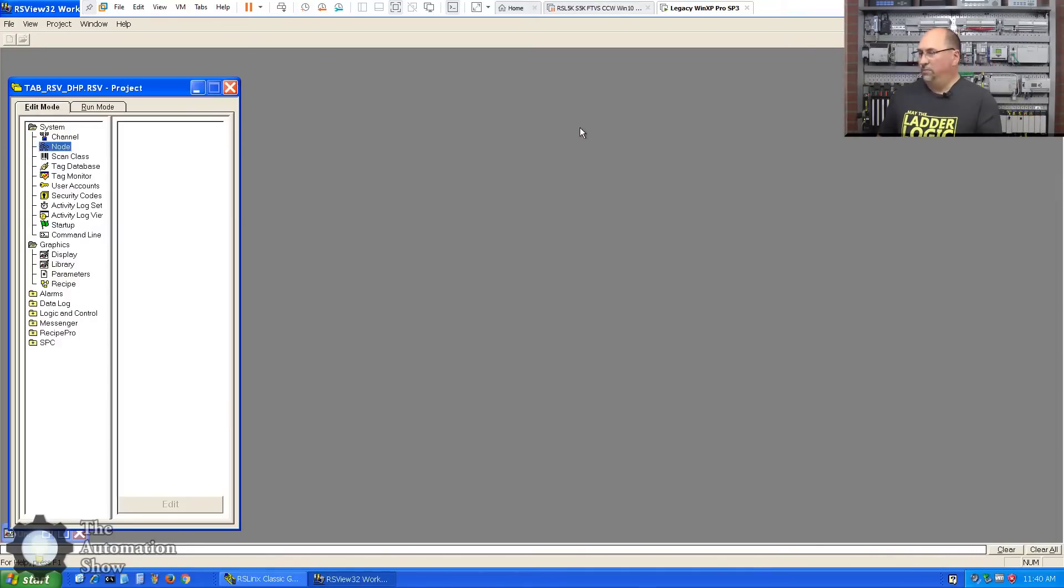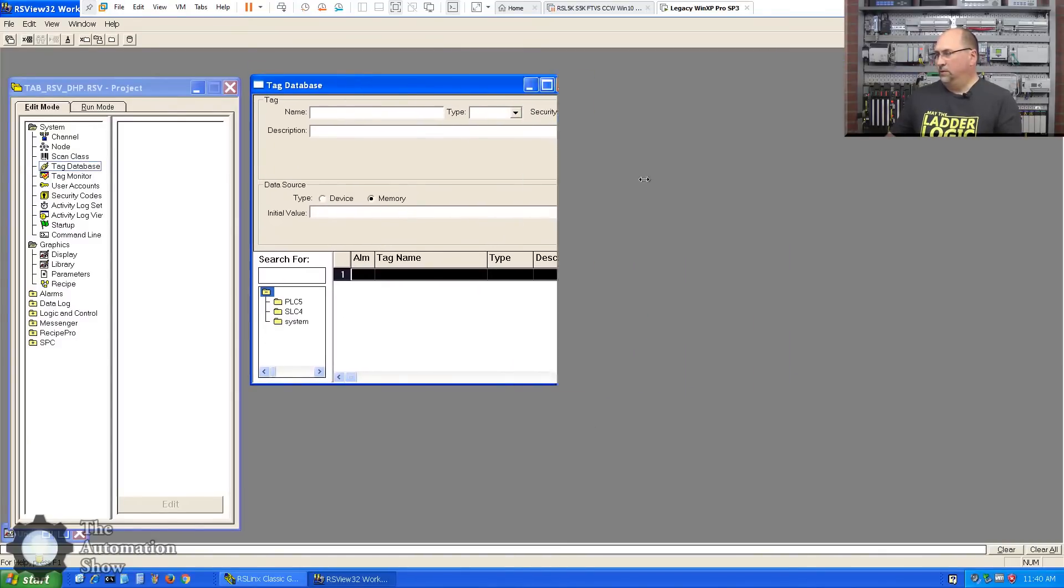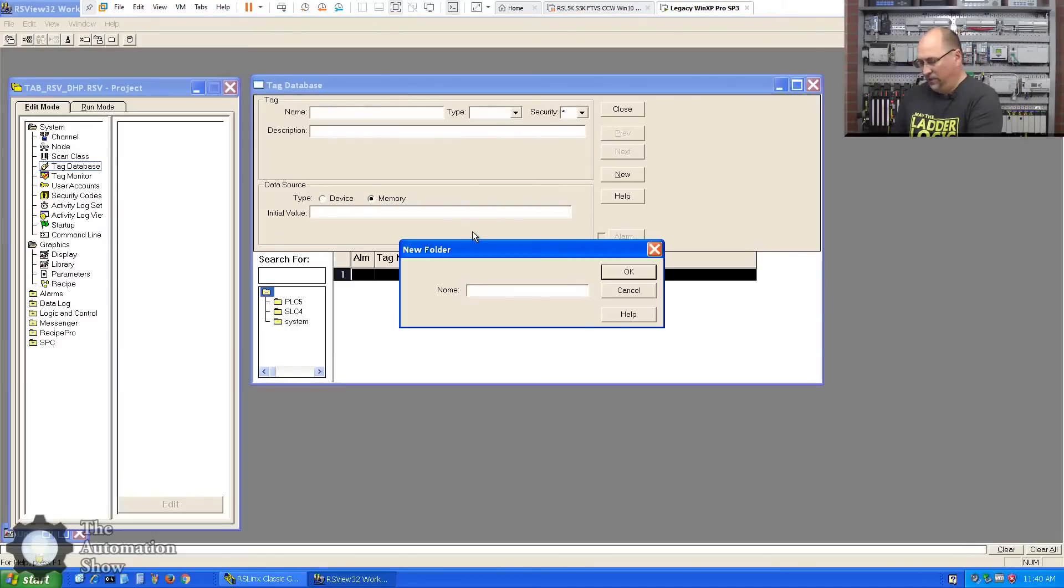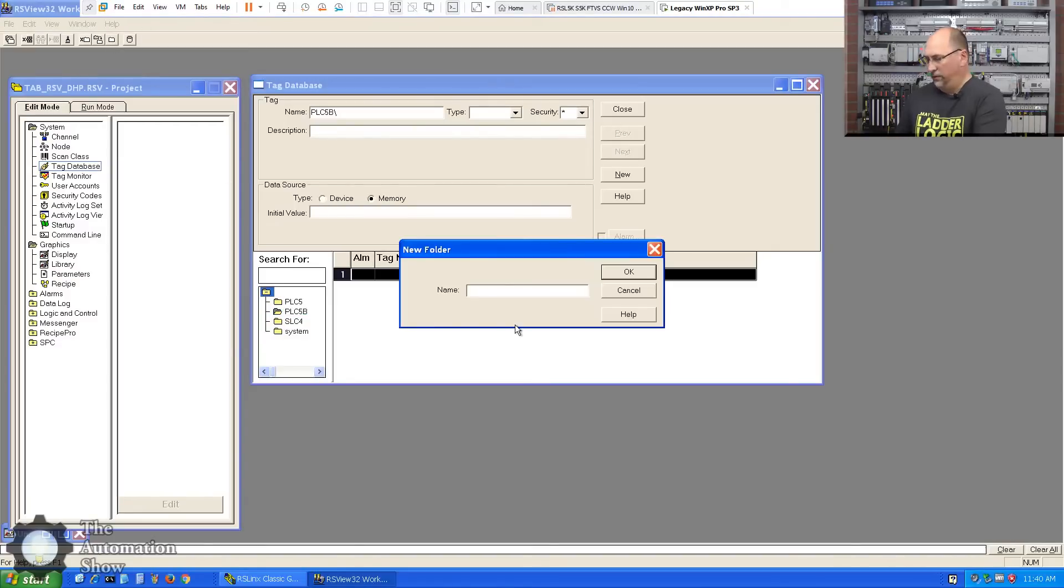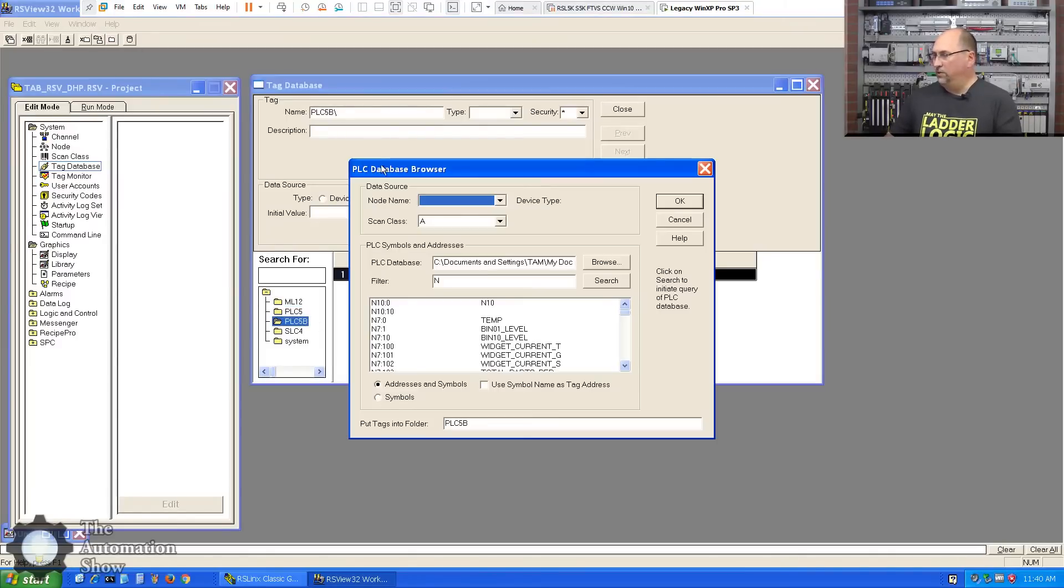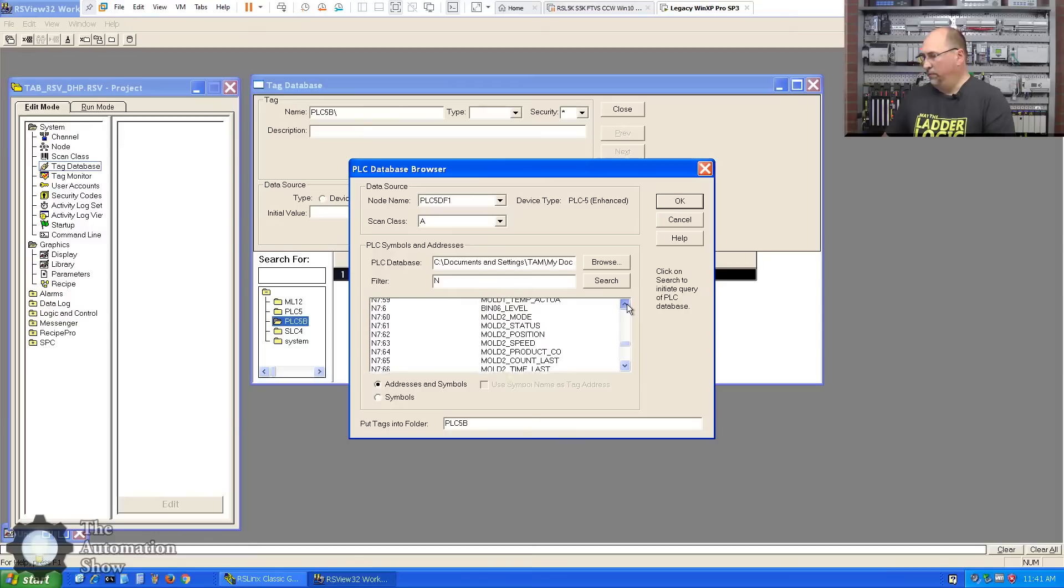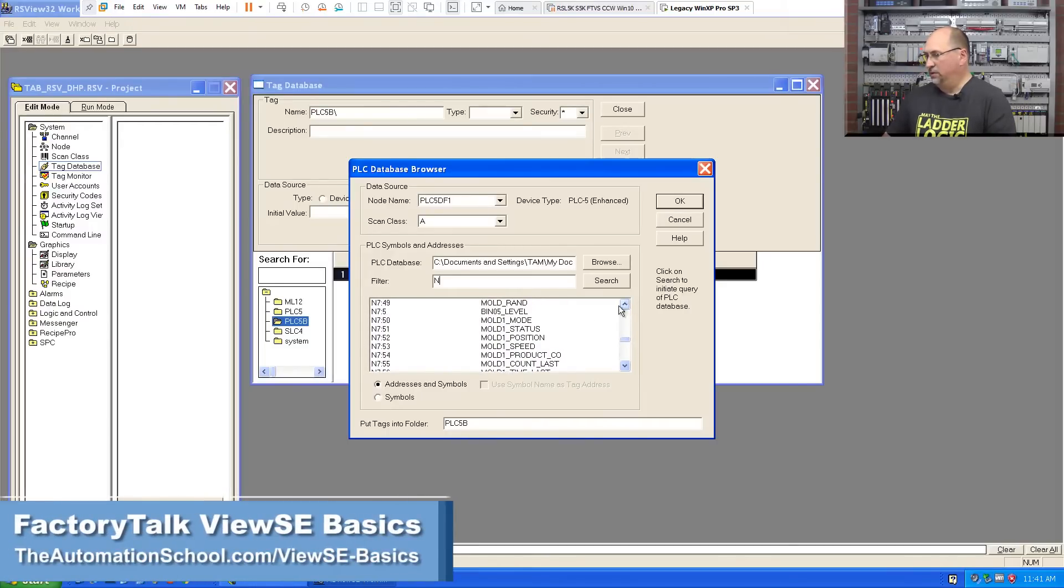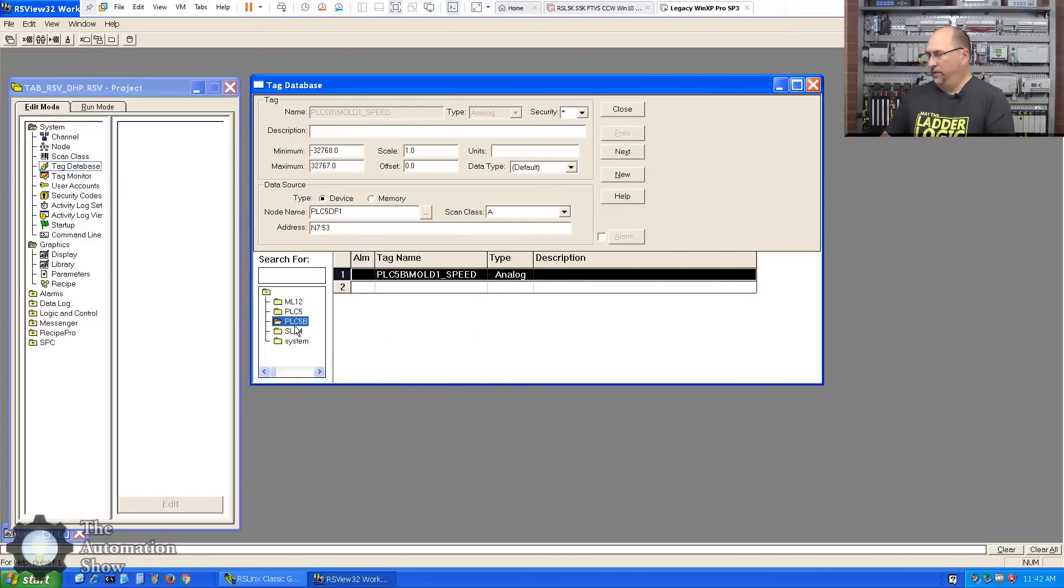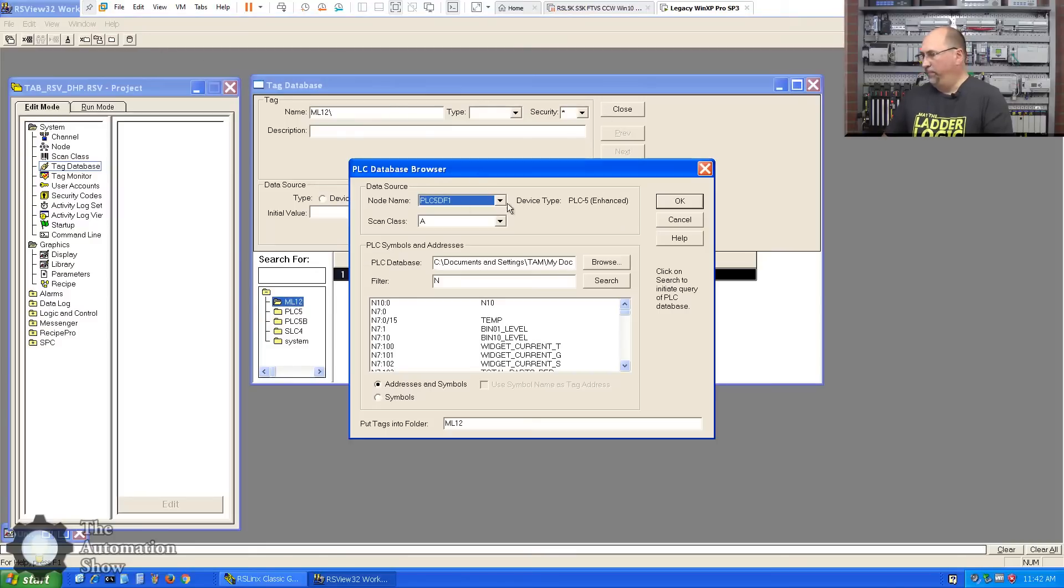Okay, now we'll do another one here and this one will be for the PLC-5 that's a direct connect via the USB and DF1 full duplex. We'll call this PLC5_DF1. That will be on the second channel, so we'll choose that station. Let's see if we can browse for it here. There it is, okay, PLC-5 Enhanced. We'll leave that like that, okay. So that's how we set up our direct drivers. Now we should also be able to create some tags quickly. And what I'll do here is I want to import all the tags like I did last time, but let's create a couple folders. A lot of advantages to having folders, so we'll do PLC5 - I'll just call it PLC5B.